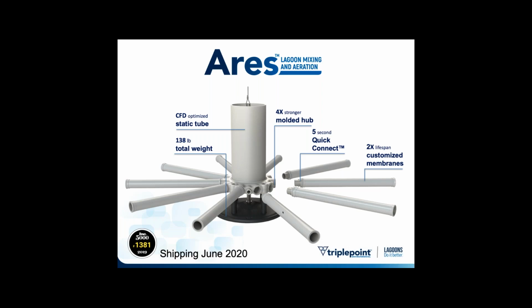The second thing is we moved to this quick connect concept here. So our old unit had threads, and a lot of fine bubble diffuser systems have threads where you're threading the diffusers into an air manifold of some kind. With our new design, this is a quarter turn quick connect. So you put it in the socket, you turn it a quarter, it snaps, it seals. So it makes it very easy both to install the diffusers, to maintain the diffusers, and to move this unit around the site, because you're not going to screw these diffusers on until the absolute last possible minute when you're about to plunk it in the water. So it really increased the overall user friendliness, I should say, of the unit.